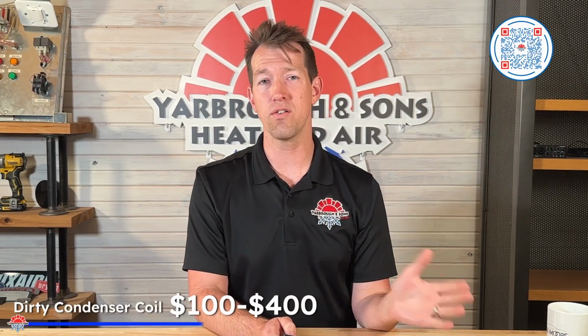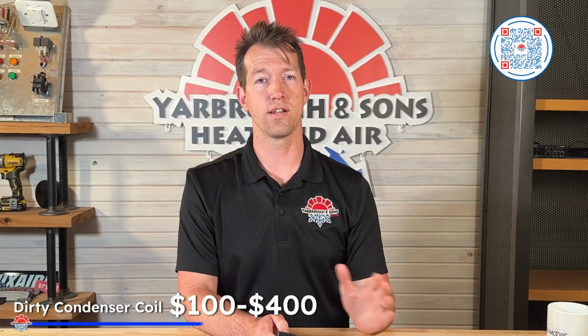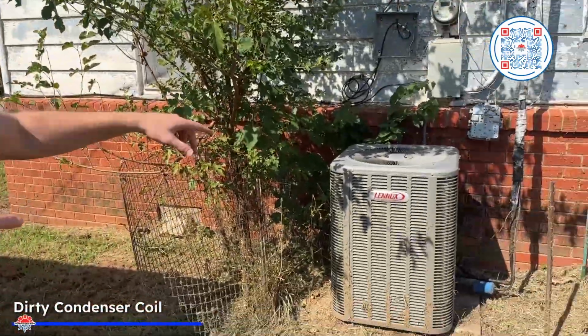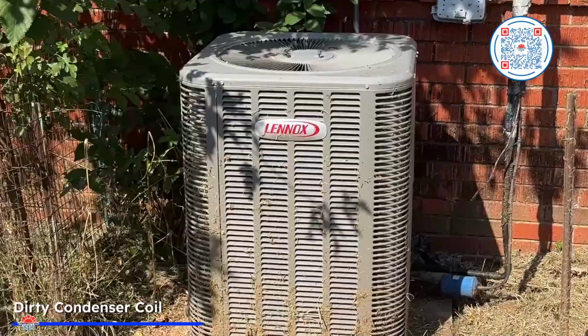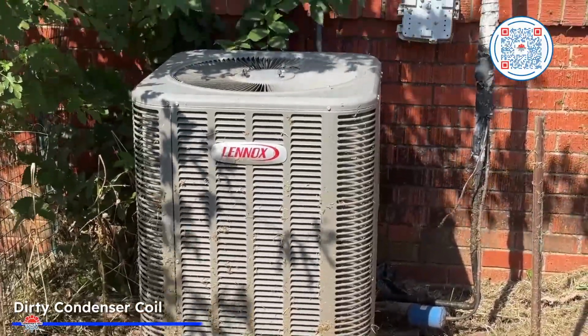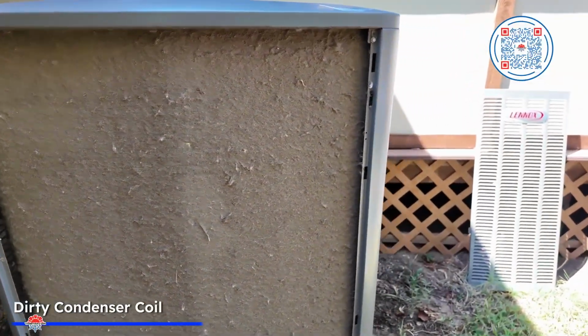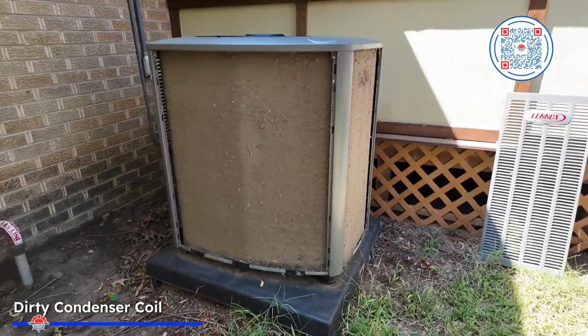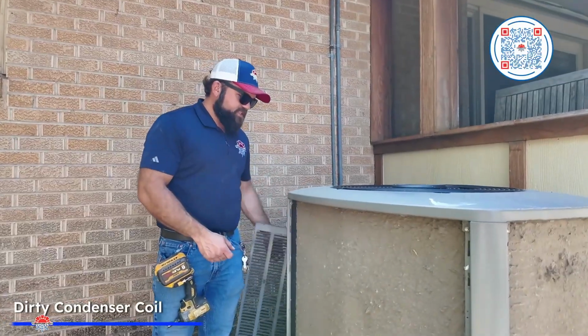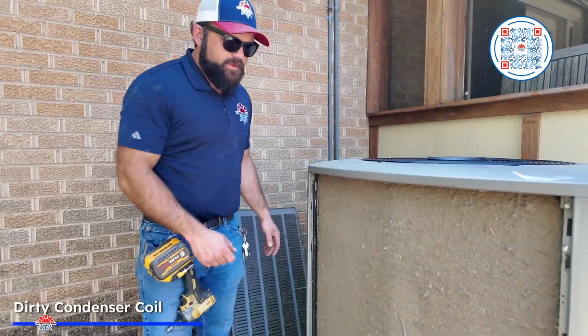Dirty condenser coil. This ranges somewhere between 100 bucks to $400. All right, so the condenser is your outdoor unit. So it's the big metal box sitting outside your house with a fan on top. Inside it are coils that release heat from your house to the outside air. When those coils get clogged, the system can't shed heat efficiently. It runs harder, longer, uses more electricity, and can't maintain your set temperature.